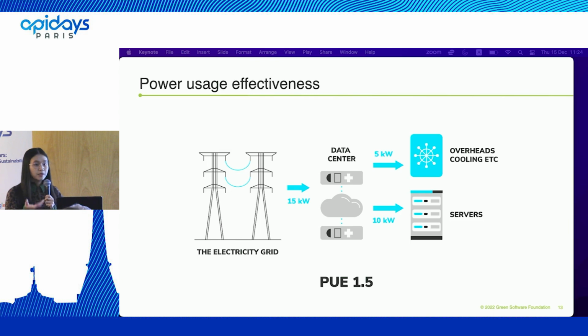Another way we can think of PUE is as a multiplier for an application's energy consumption. It's a way for software engineers to conceptualize how much energy is needed to support our applications in a particular data center. For example, if our application consumes 10 kilowatt hours and the PUE of the data center is 1.5, then the actual consumption we need from the grid is 15 kilowatt hours, where 10 kilowatt hours go to the servers running our applications, and 5 go towards overhead activities.